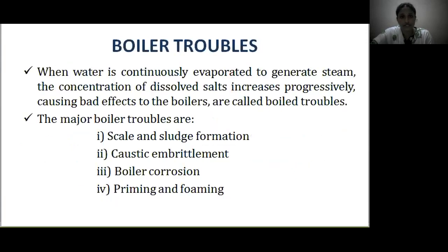When the water in the boiler is continuously evaporated to generate steam, the concentration of dissolved salts increases progressively, causing very bad effects to the boiler — called boiler troubles. The major boiler troubles are scale and sludge formation, caustic embrittlement, boiler corrosion, and priming and foaming.